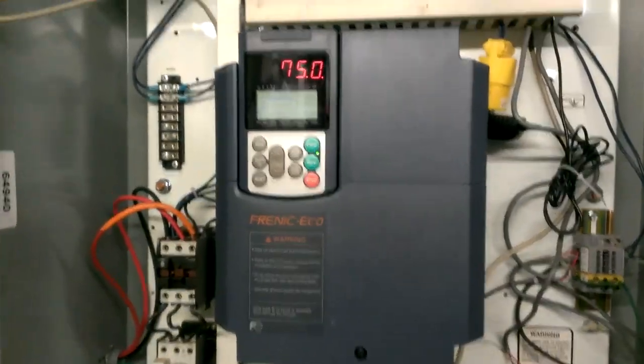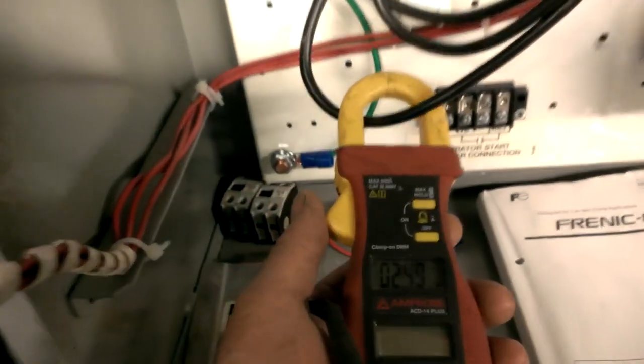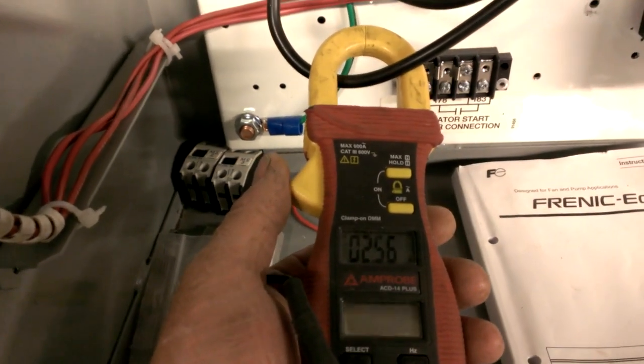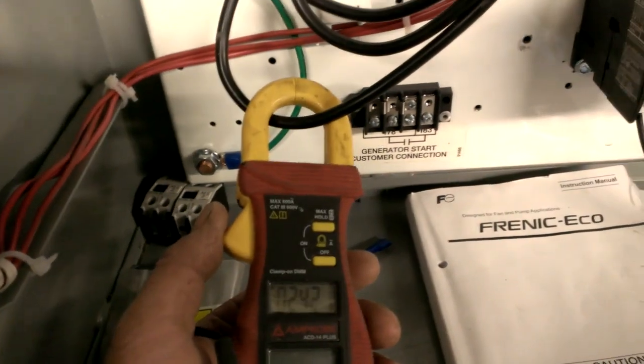There's not very much demand. It's at 460 volts, 2.5 amps, 2.6 amps. I've seen it all the way down to like 1.8 when there's probably not very much flow.